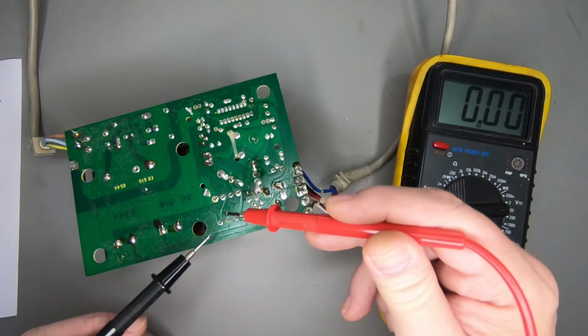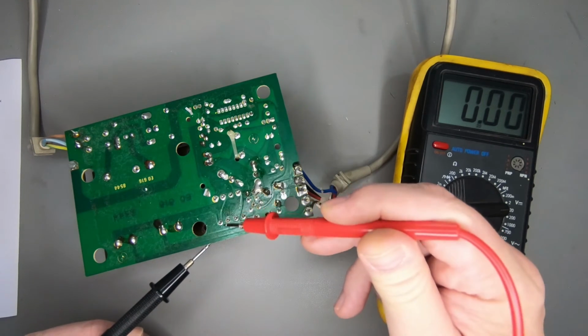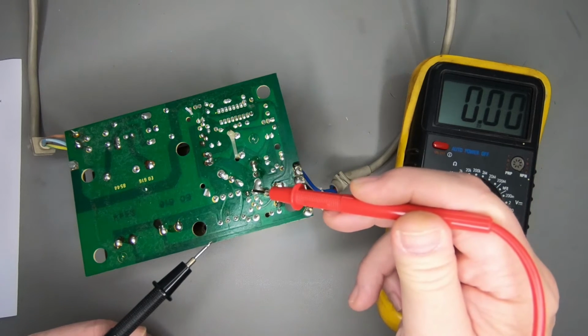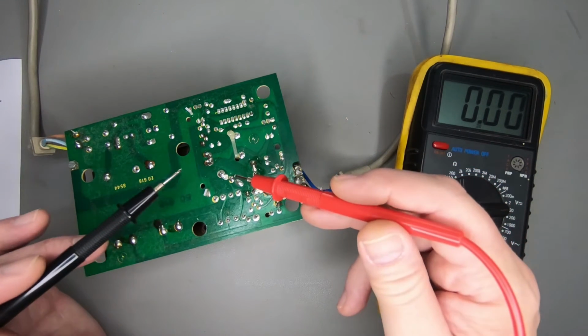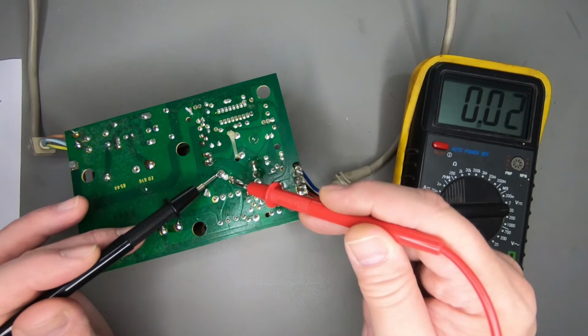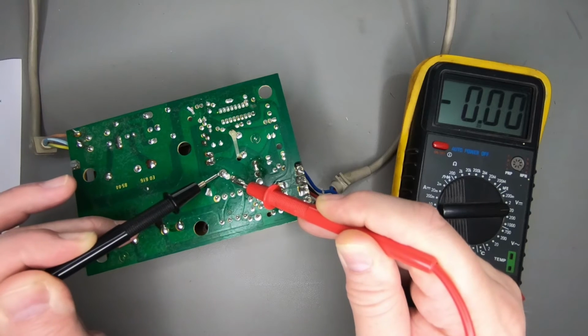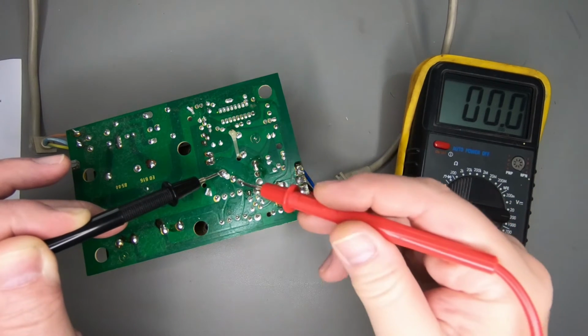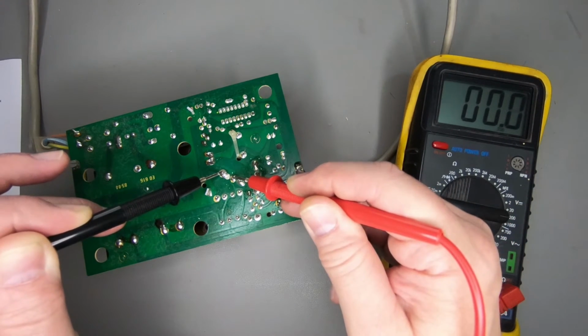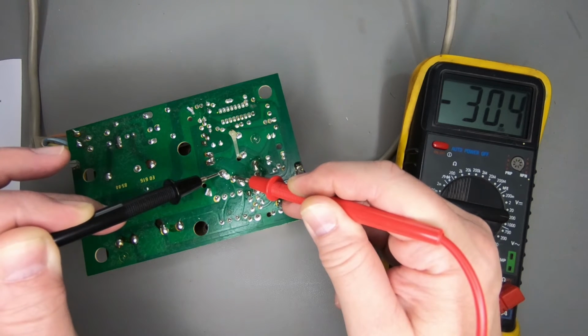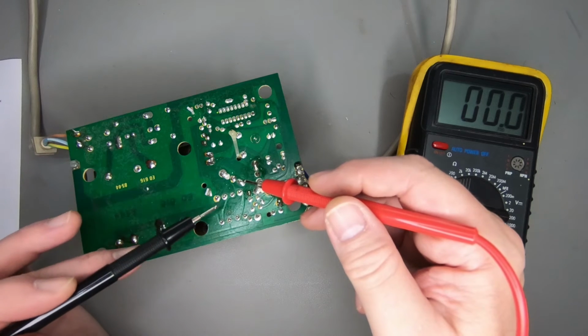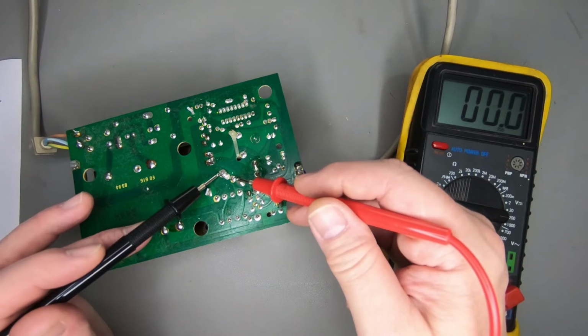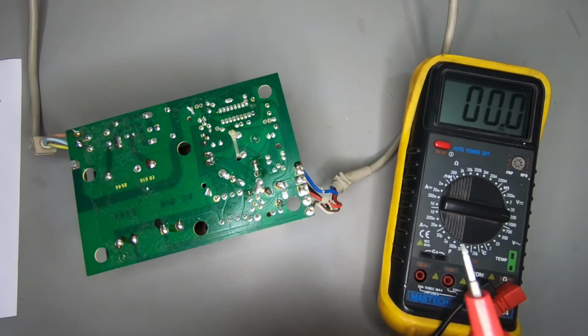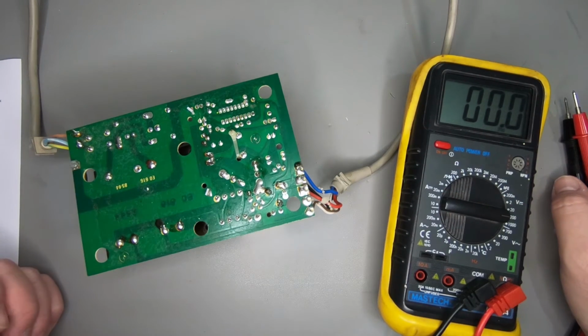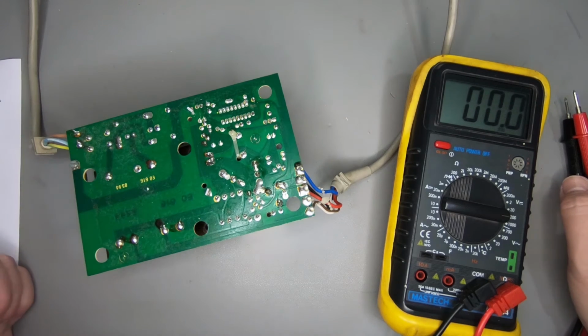So we've got our rectifier, the 4 diodes, and then 2 smoothing capacitors. So let's check across one of those smoothing capacitors. 30 volts DC. This is after the rectifier diodes. It's 30 volts DC. So we know the rectifier is good. The capacitor must be good. It's the regulation circuit after that.